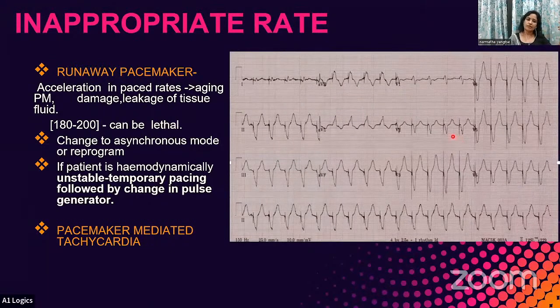There is another terminology called runaway pacemaker. This is mostly seen when there is an aging pacemaker where there is any leakage. Here the rate is very high, more than 180, 200, and it can be very lethal. Immediately the patient should be changed to the asynchronous mode, or temporary pacing should be done, and the pulse generator should be changed.